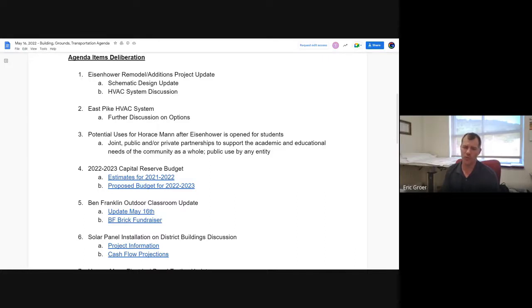Geothermal works really well if you have a nice cubed building, a 4 or 5 story office building with exterior exposure and a lot of interior exposure, and then it runs year round. When you have a building like that, you can see some pretty significant savings with geothermal because a lot of times you're not running compressors, you're moving heat and cooling back in and out. But with the K through 12 school being off in the summer, and the fact that it's a single story L-shaped building with mostly exterior exposure, most of the time this building is going to be in all heating or all cooling mode. There's not much opportunity to transfer heat and cool between different exposures.